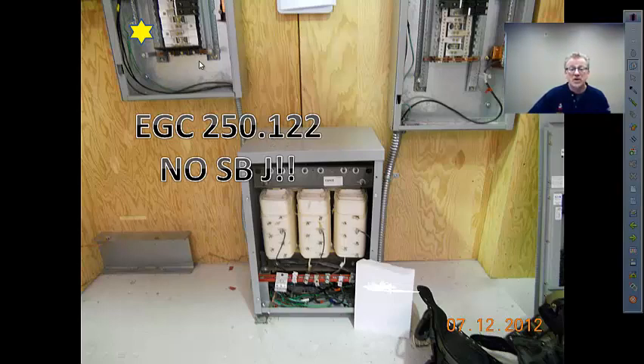And there's no system bonding jumper. No system bonding jumper up here. This is grounding. It's a feeder with a breaker. We have an equipment grounding conductor. And you may need to bond that flex. If the flex is not bonded, maybe grounding is interrupted by reducing washers or something, then we'll need a bonding bushing. And certainly the simplest place to put a bonding bushing is up here in the panel board where you can get your hands on it. Once it's bonded on one end, the flex is bonded. We don't have to put a bonding bushing on both ends. The other end may or may not, depending on the wire size, need a plastic bushing. Conductors 4 and larger require an insulated throat fitting or insulating bushing.